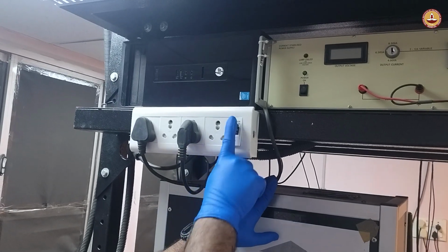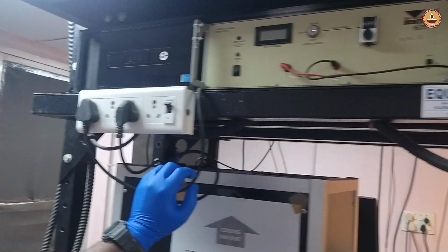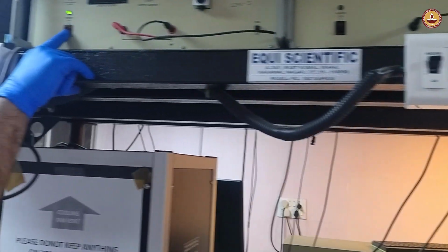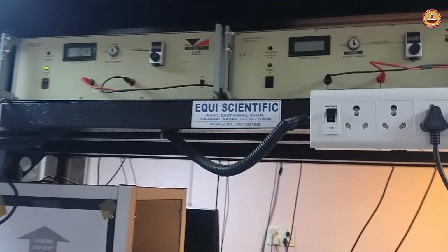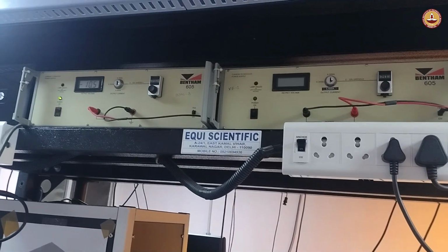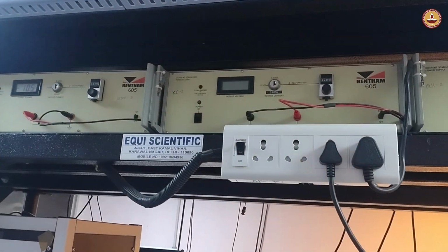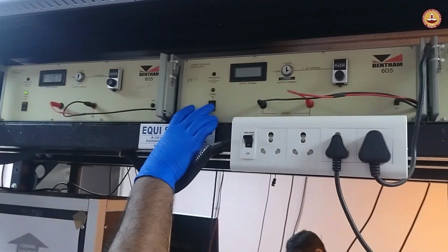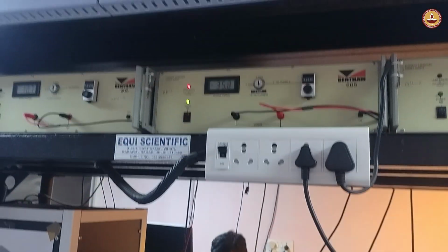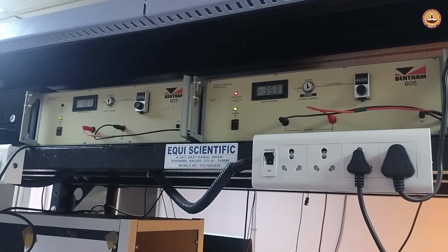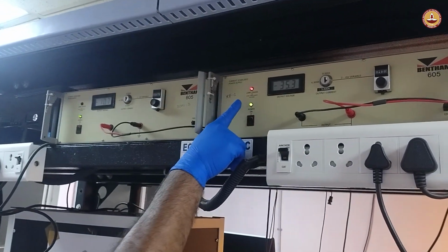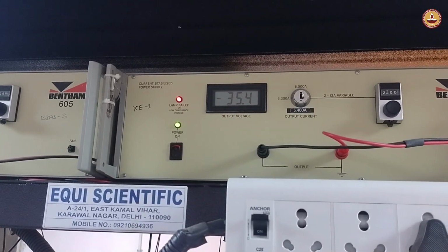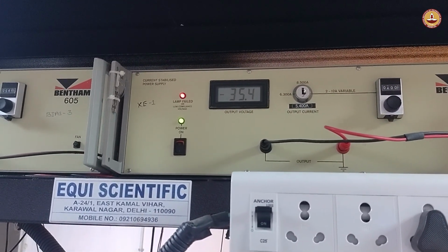After confirming all precautions are taken care of, turn on the main power supply. Switch on the bias lamp and the xenon lamp. After turning on the xenon lamp, wait for the lamp fail indicator to turn off. This indicates that the cooling system and the xenon lamp are working properly. Once the lamp fail indicator goes off, turn on the quartz halogen lamp.